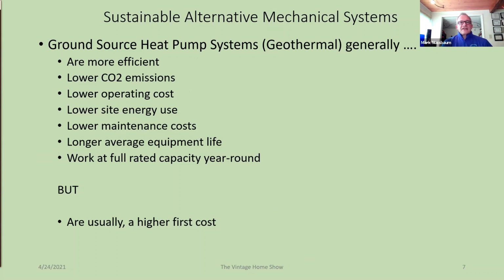So, generalities here, just the reasons why we might consider looking at geo: they are typically more efficient than all other available residential systems. They have lower CO2 emissions, so they're good at reducing that footprint, lower operating costs, and lower site utility use. In a traditional system, you might have a gas furnace and an electric air conditioning unit. These are all electric systems, so you're going to get rid of your gas service or gas load and have an all electric winter and summer. You've got lower maintenance costs because you have no outside equipment. You have a longer average equipment life, maybe 5 to 10 years typical over air source equipment, and they work at full rated capacity year round, which is kind of a big deal.